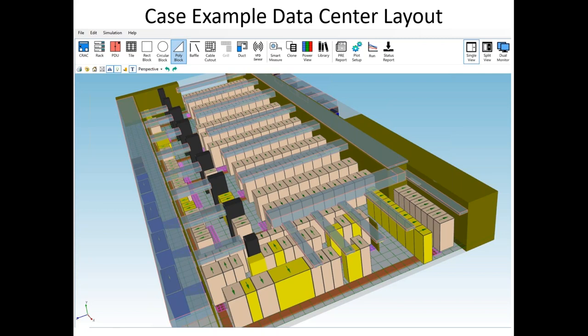The rack is effectively a block with an inlet-outlet boundary condition pair — air coming in one side, going out the other. Fidelity can be turned up, but you run into increased time when you do that. For a data center at this level of granularity, it's easiest to use a coarse level of representation for the racks and work with average watts per rack.